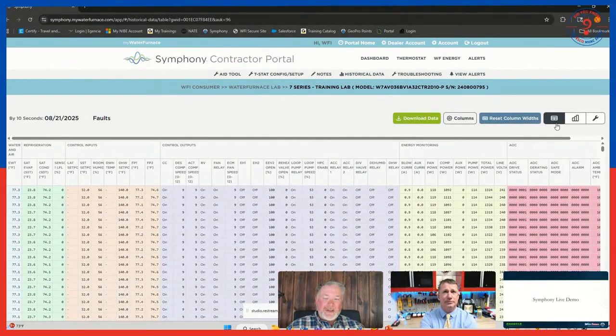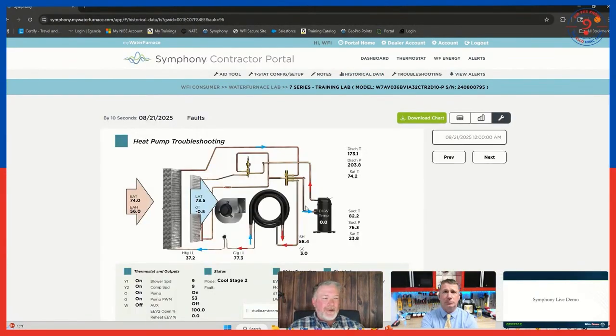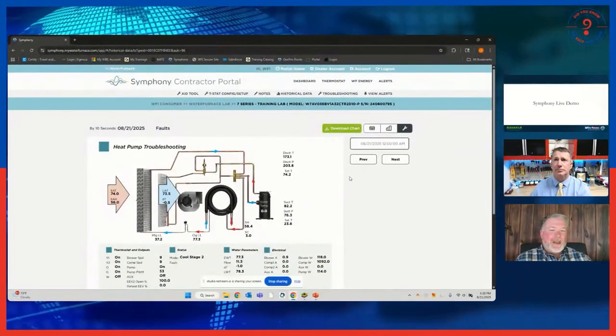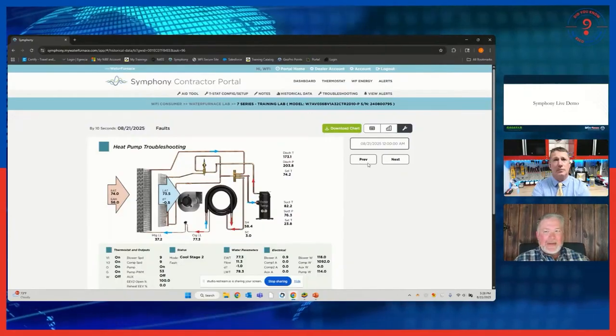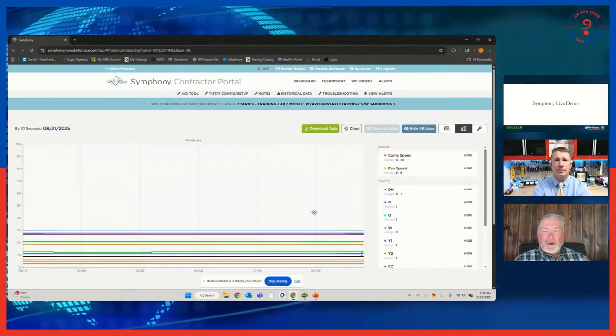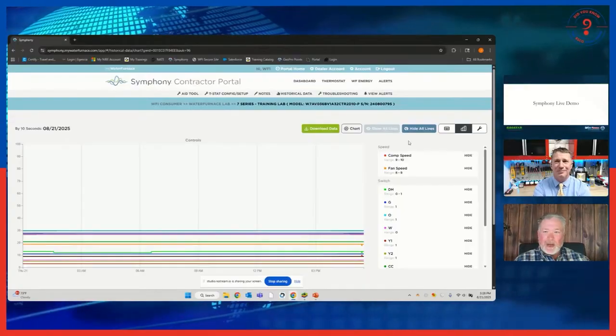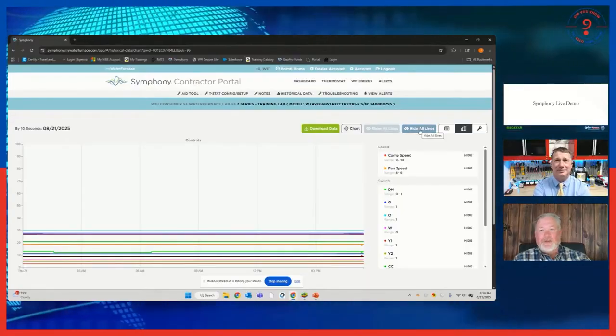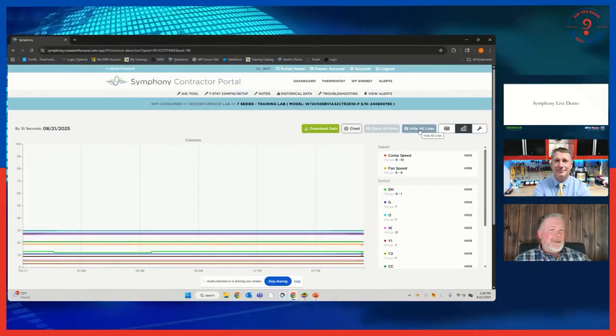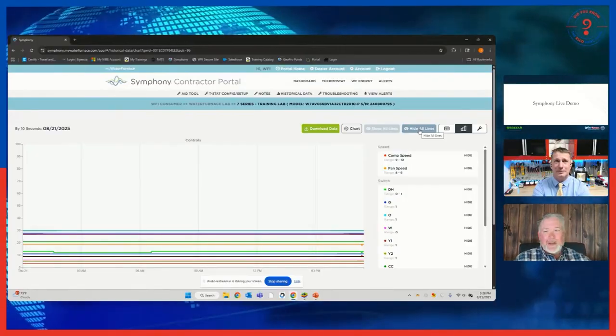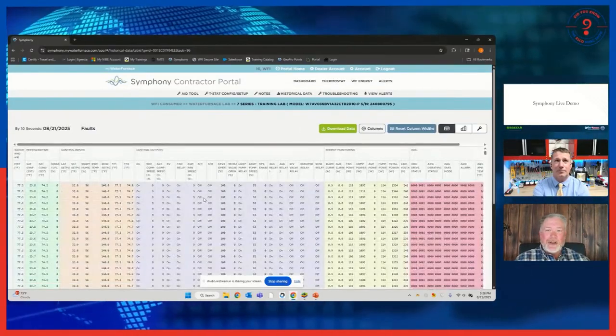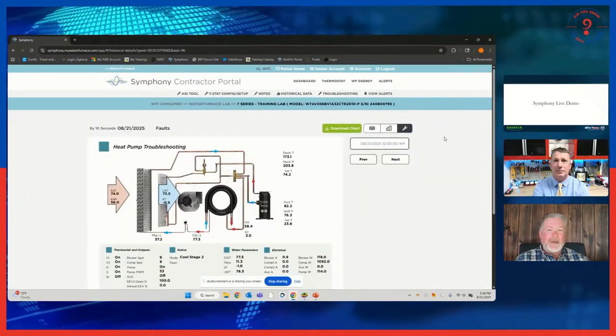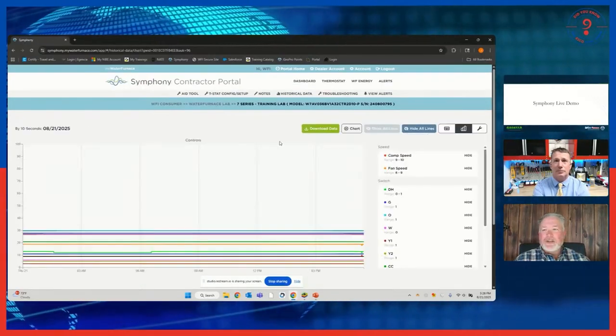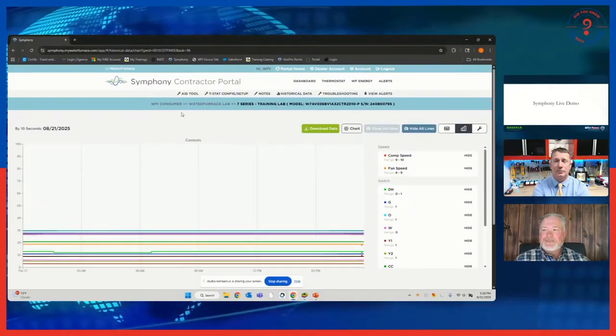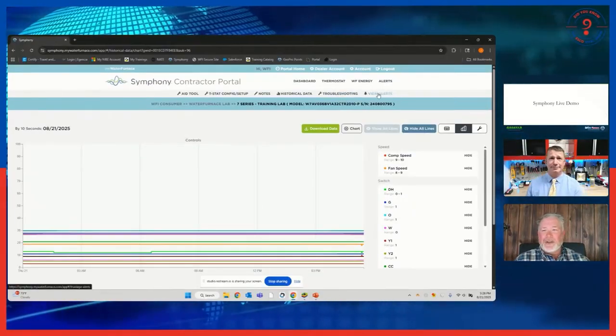Once it does that, I can go back over to the troubleshooting chart that we just had up and see what it was doing when that fault occurred. At that time, I can advance it or bring it back 10 seconds at a time. I can go into bar graphs with whatever information I want. I can make it just show suction pressure only, for example, or maybe just delta T on the air side or water side. I can see that in a chart, I can see it in a bar graph, or I can see it on the troubleshooting chart itself. So it makes it kind of nice to see what's going on there. So all kinds of stuff we can do on that side.